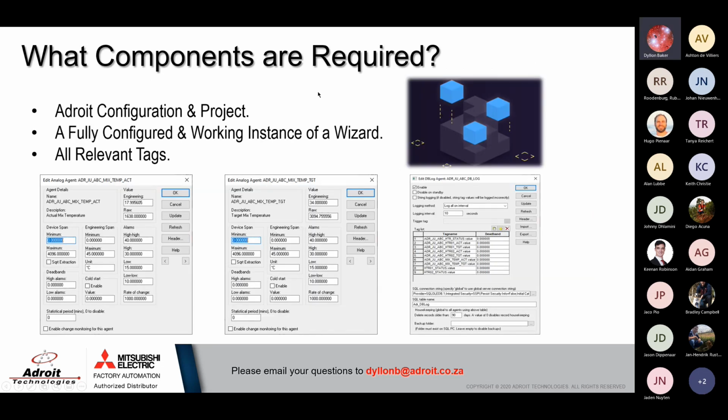In terms of the main challenges behind simply using a wizard over object model, any required SCADA-related configuration of an object or piece of equipment would be left up to the user to manually implement for each instance of the wizard. Thanks to object model, the user only needs to implement the required SCADA-related configuration to one object, and from there, the user can generate an object model template, which creates a foundation for multiple instances to be deployed with the same configuration.